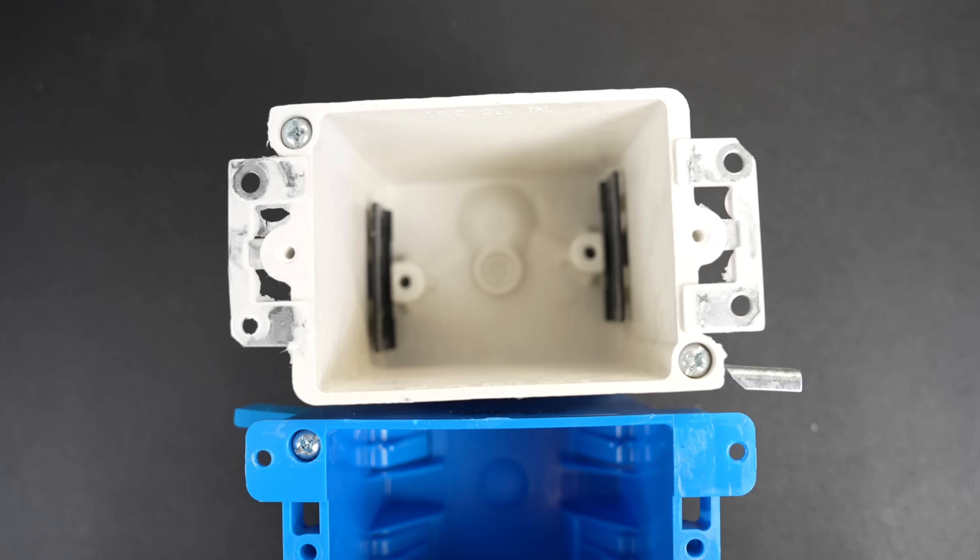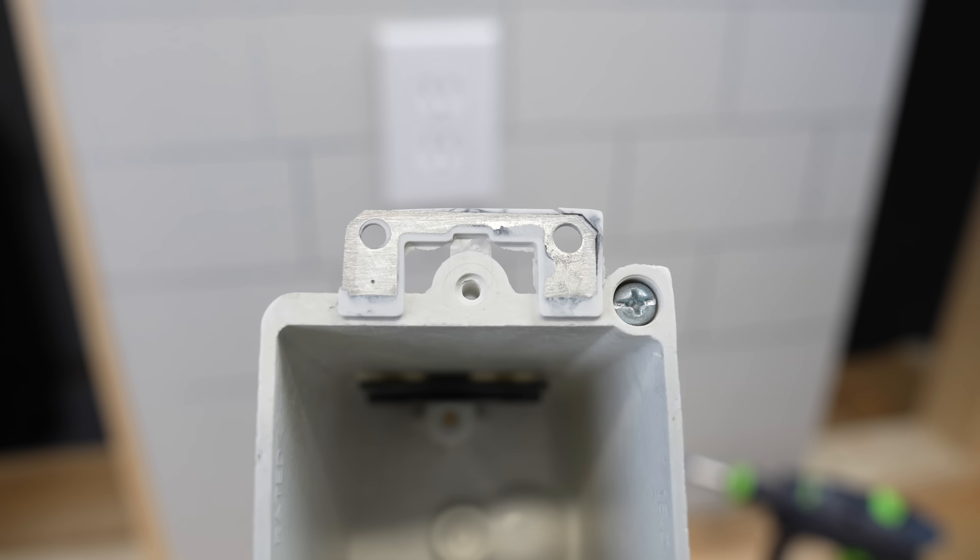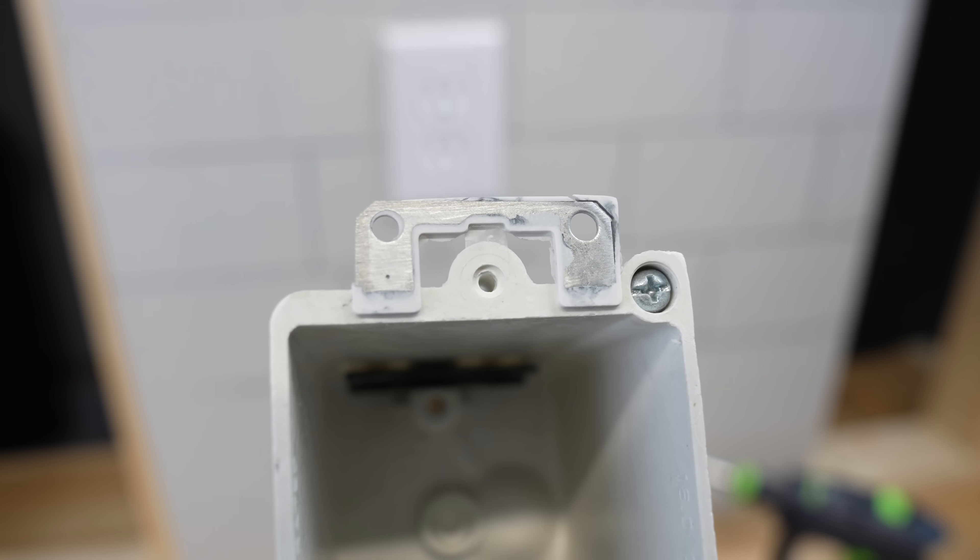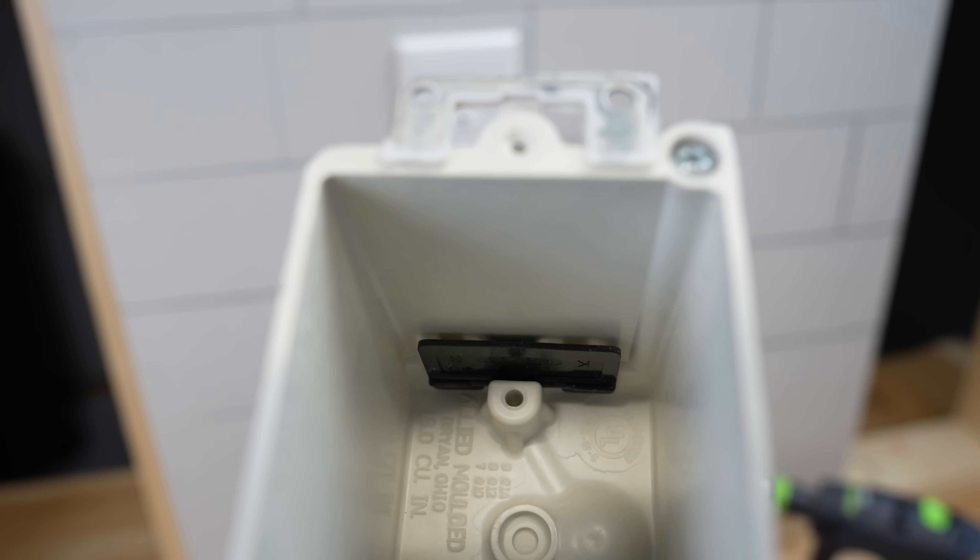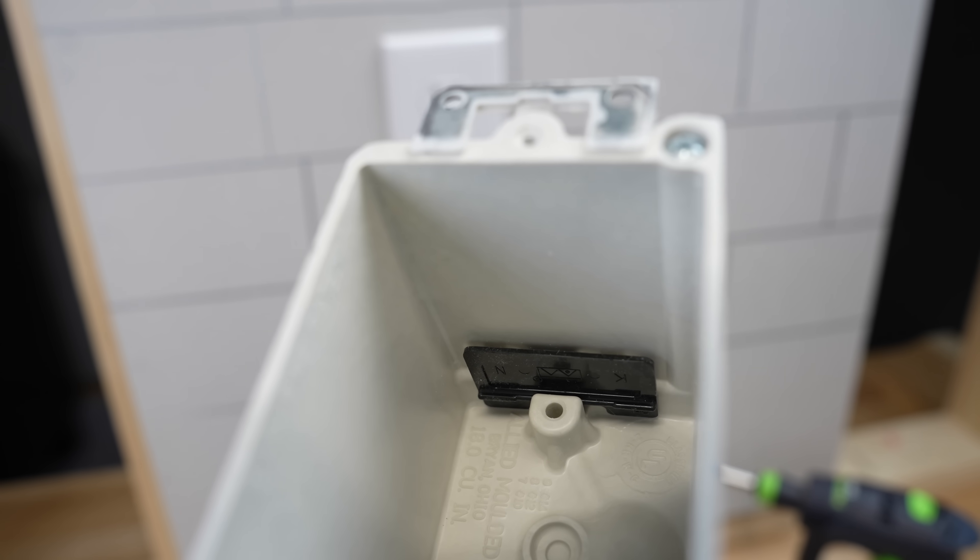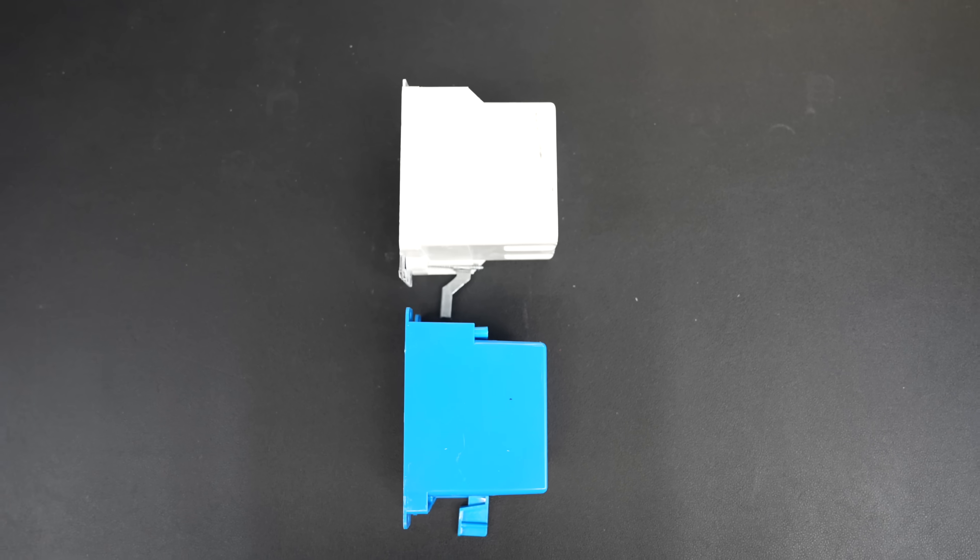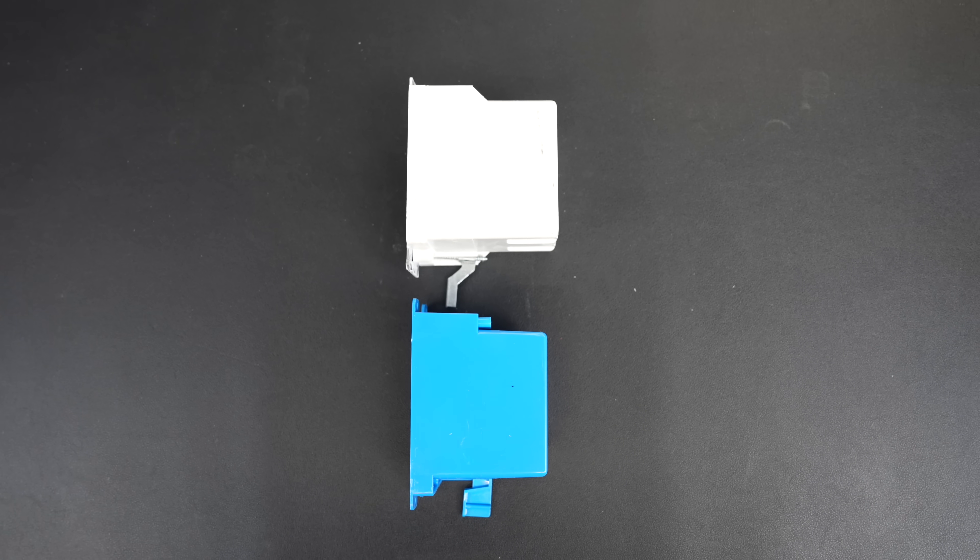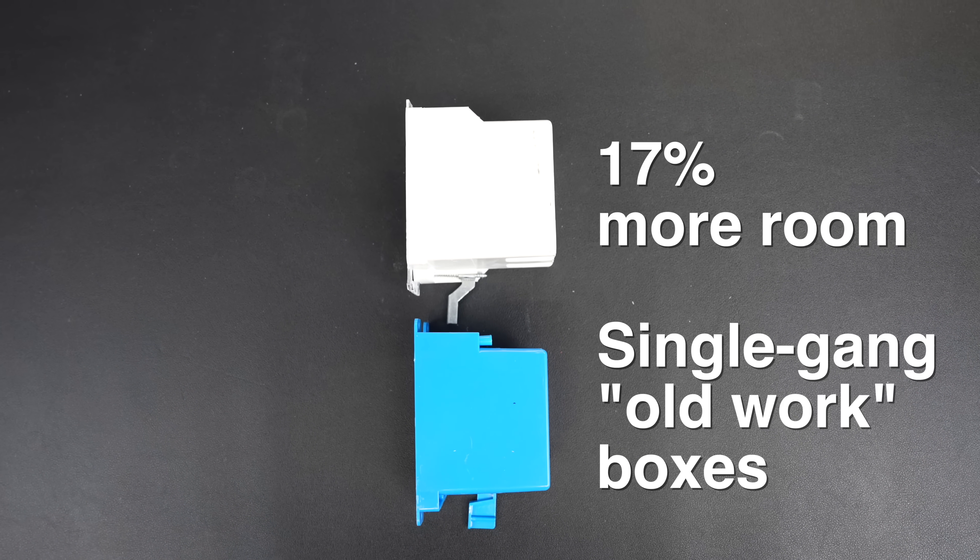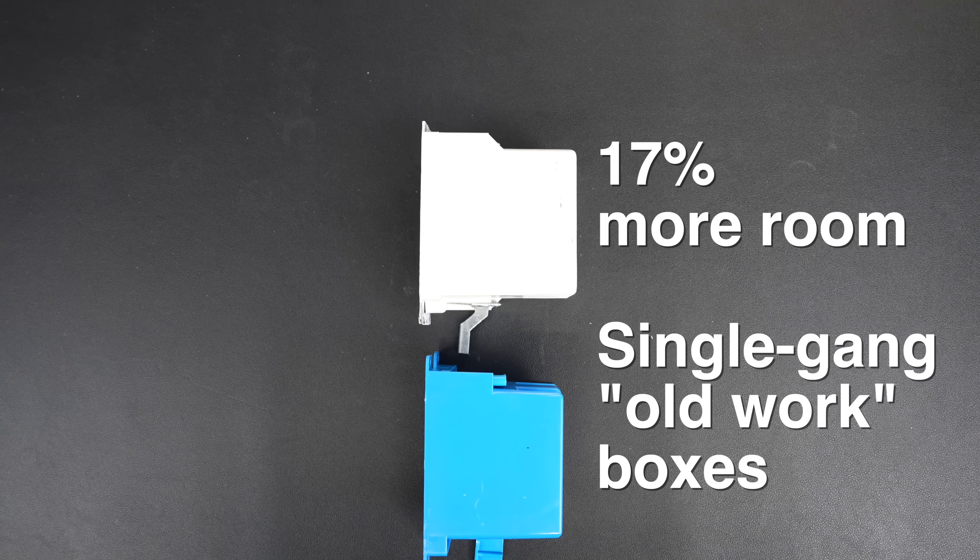Now let's compare that single gang plastic box to a fiberglass box. The difference here is this fiberglass design molds in the metal components along with the cable strain reliefs. They don't require all that extra molding. That means the inside of the same sized box is almost 20% larger than the equivalent plastic box.